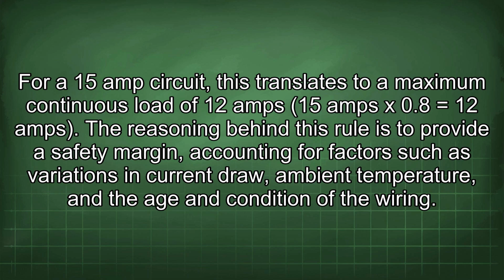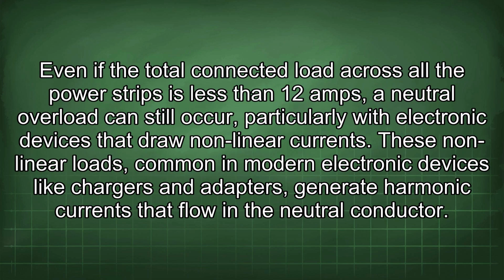15 amps x 0.8 equals 12 amps. The reasoning behind this rule is to provide a safety margin, accounting for factors such as variations in current draw, ambient temperature, and the age and condition of the wiring. Even if the total connected load across all the power strips is less than 12 amps, a neutral overload can still occur, particularly with electronic devices that draw nonlinear currents.